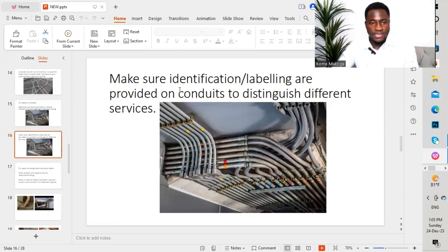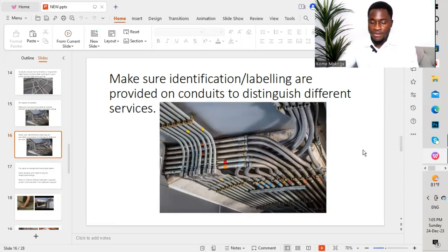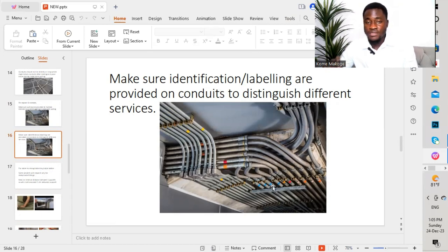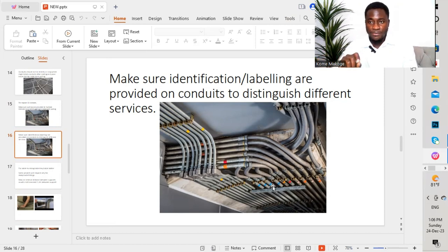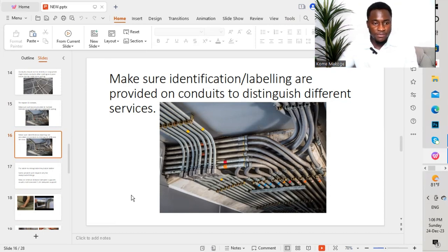Make sure identification labeling is provided on conduits to distinguish different services. As you can see in the graphic, we have yellow labeling, red, and blue — all these different labelings signify different services. You go through the project specification and ensure that you provide proper labeling for the different services. Suppose we have lighting, small power, fire alarms, and CCTV cameras — we have to provide different labeling as per the different services as mentioned in the project specification.